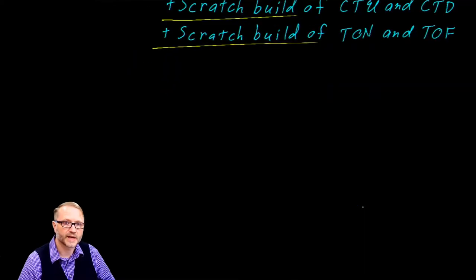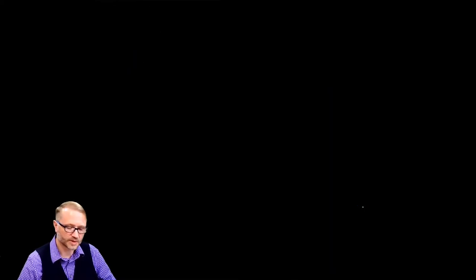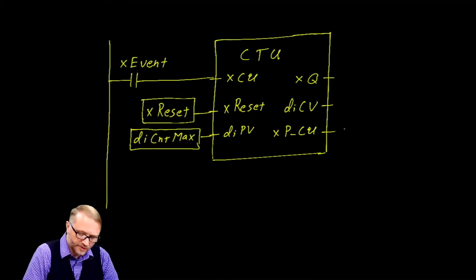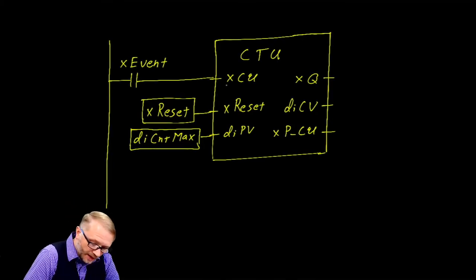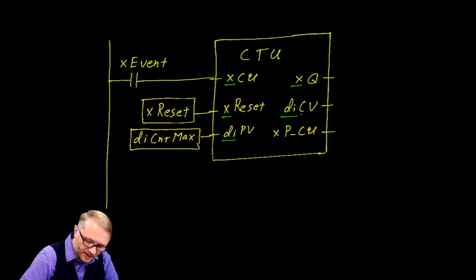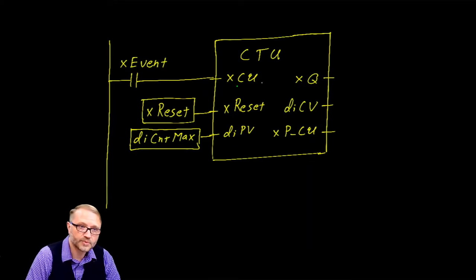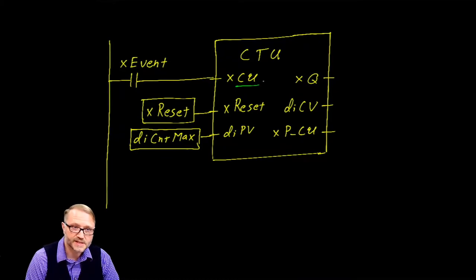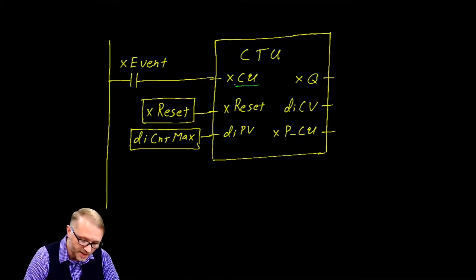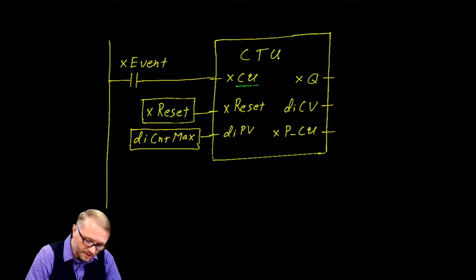We'll start by looking at the count up block. This block should look familiar. However, I've taken the liberty of adding the prefixes for our data types before each of the inputs and outputs. Our inputs are described as count up — this is an edge sensitive input. Every rising edge, the counter will be incremented.